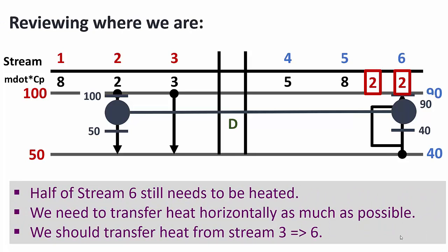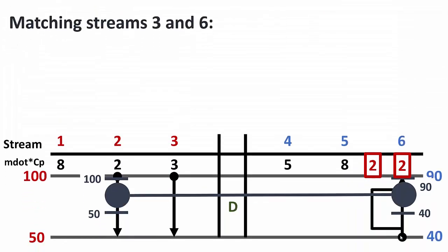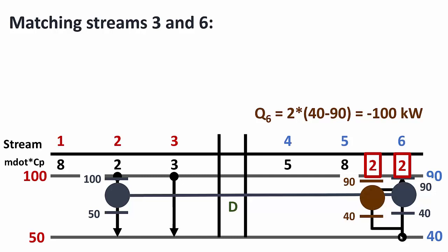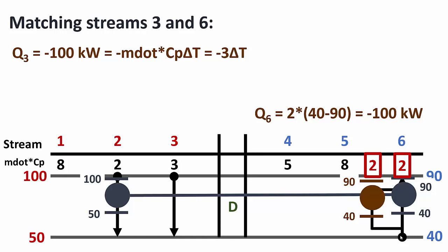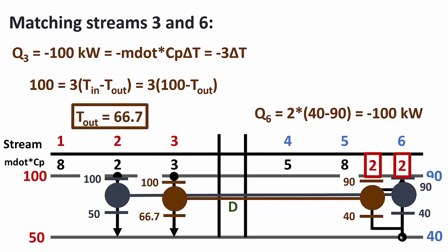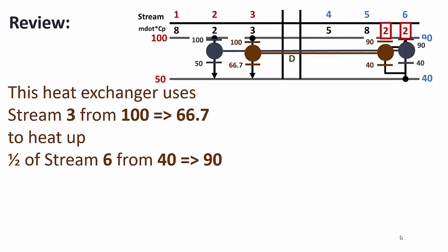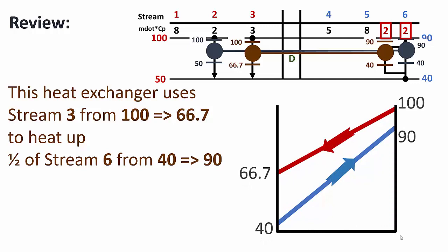Half of stream 6 still needs to be heated. We transfer heat horizontally, matching streams 3 and 6. Stream 6 half has Q = 2 × (40 − 90) = −100 kW, which is transferred to stream 3: −100 = −3 × (T_in − T_out). We specify T_in = 100°C (starting from the top) and solve for T_out = 66.7°C. This heat exchanger uses stream 3 from 100 to 66.7°C to heat the other half of stream 6 from 40 to 90°C. The temperature graph confirms the minimum approach temperature is not violated.